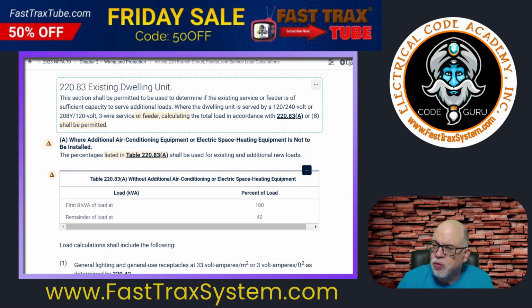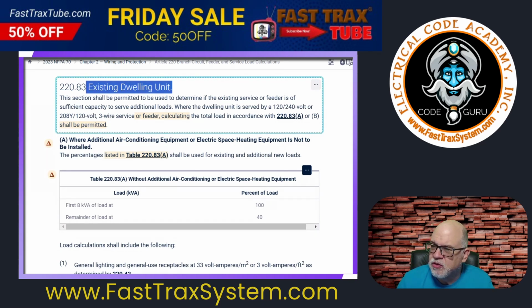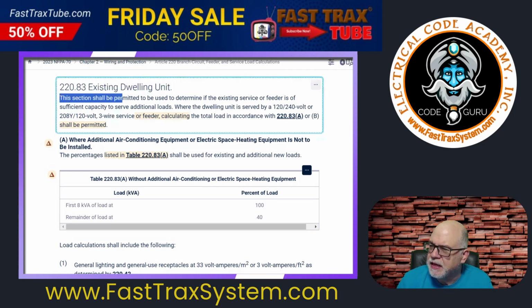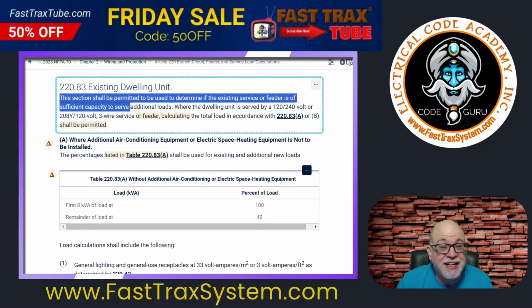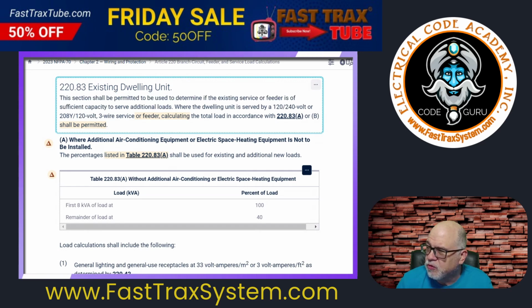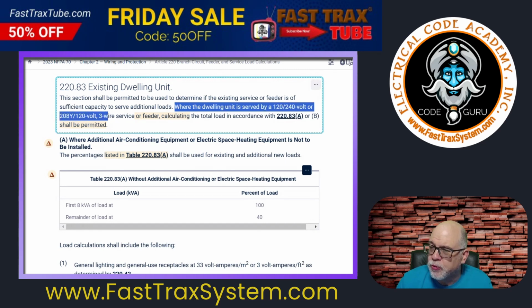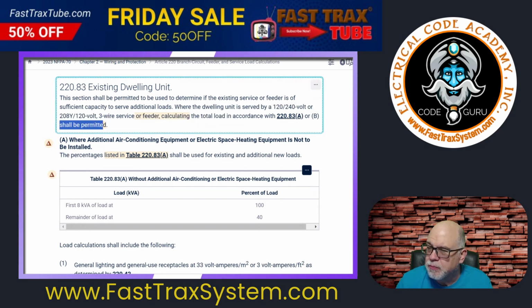So here is 220.83, existing dwelling units. It says this section shall be permitted, so it's a permissive statement, to be used to determine if an existing service or feeder is of sufficient capacity to serve additional loads. It says where the dwelling unit is served by a 120/240 volt or a 208Y/120 volt 3-wire service or feeder, calculating the total load in accordance with 220.83(A) or (B) shall be permitted.